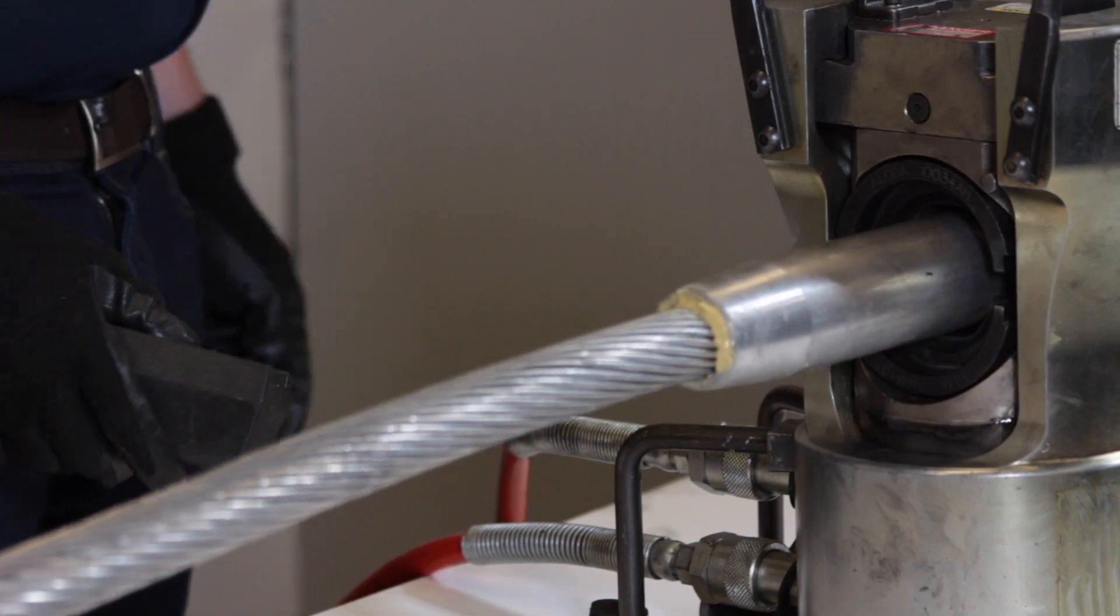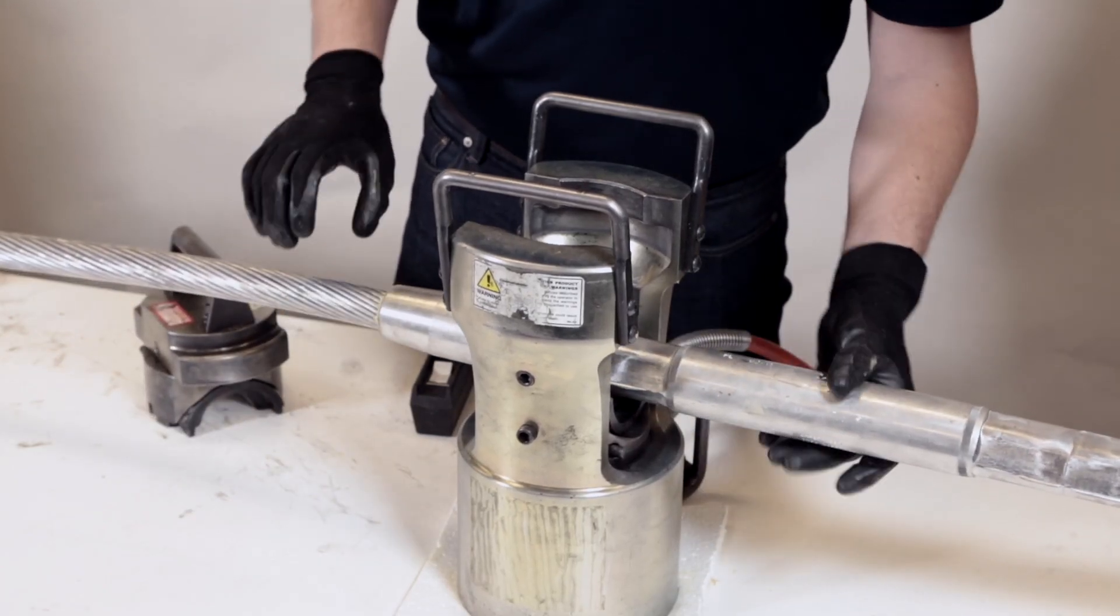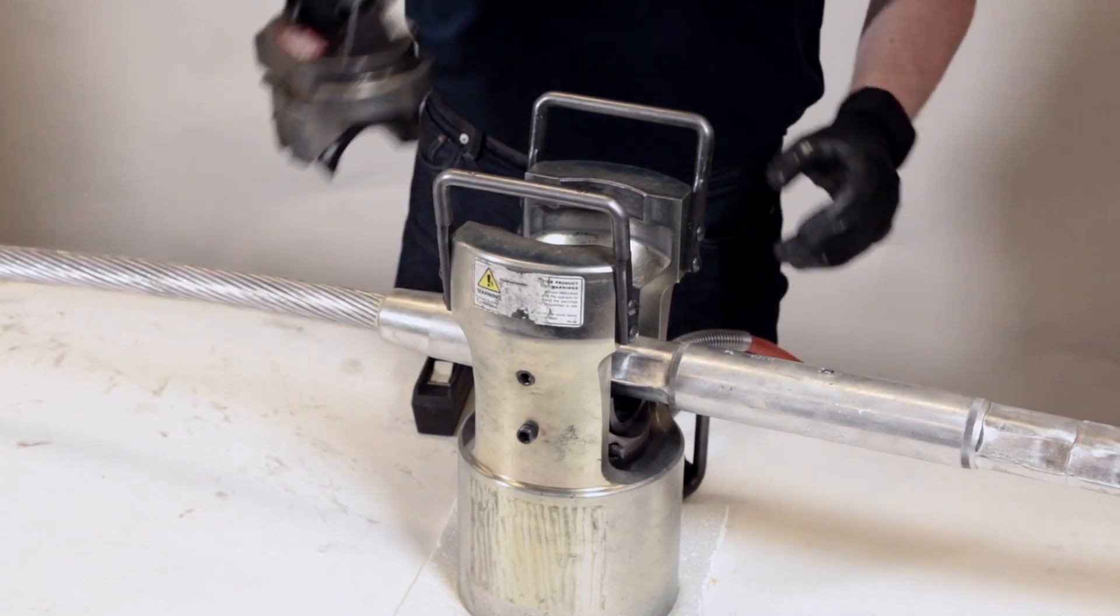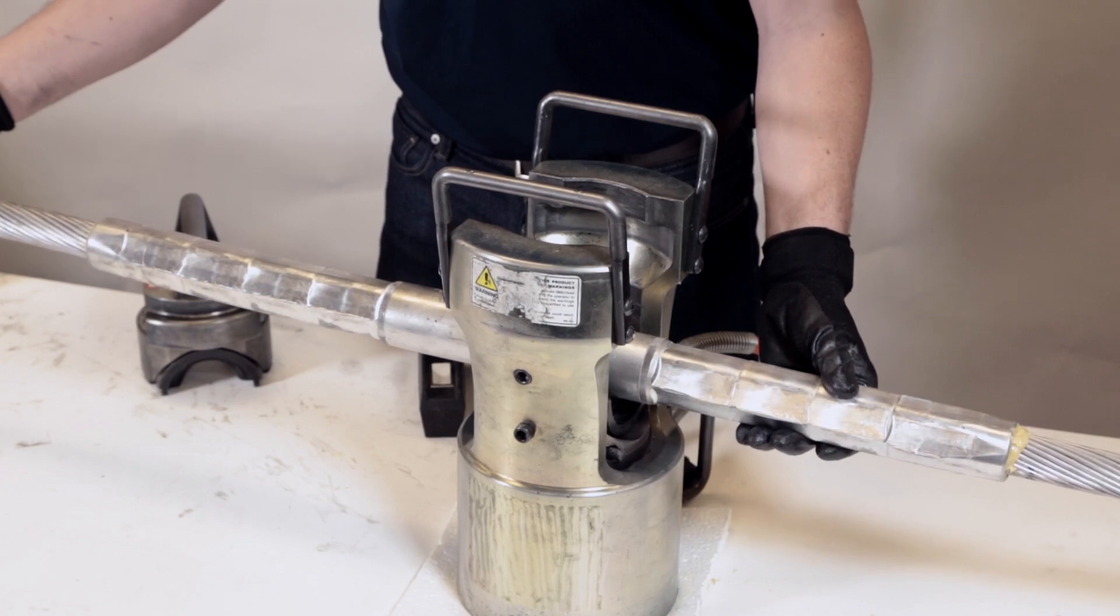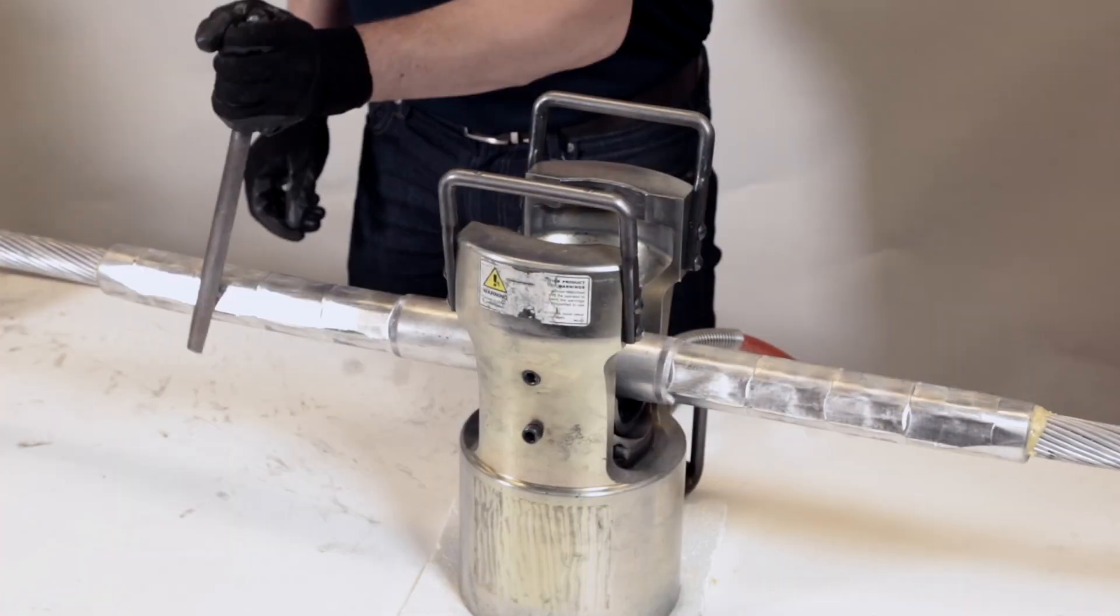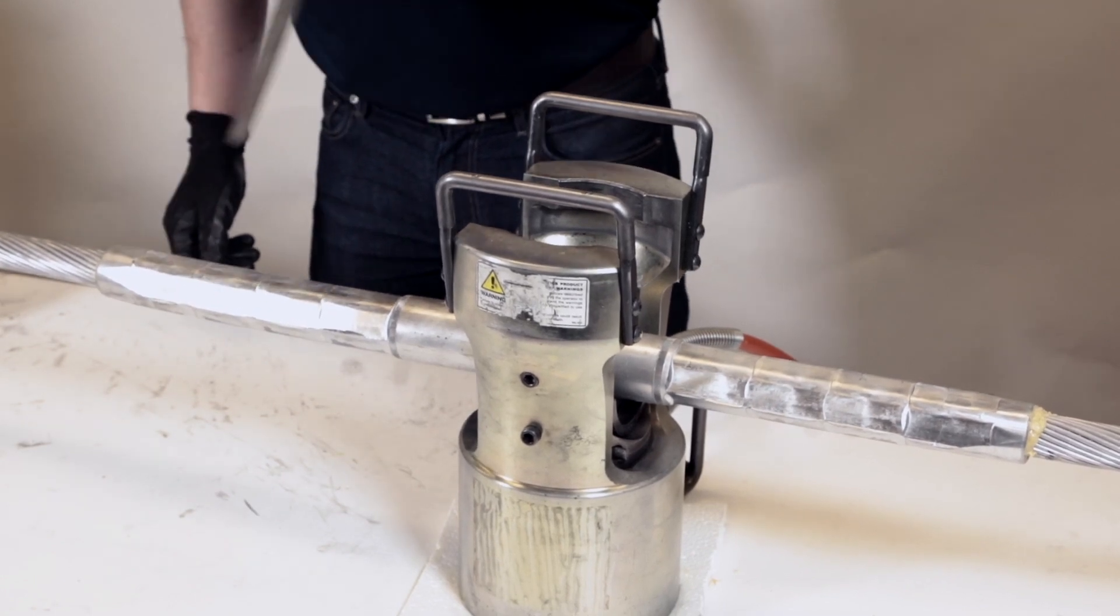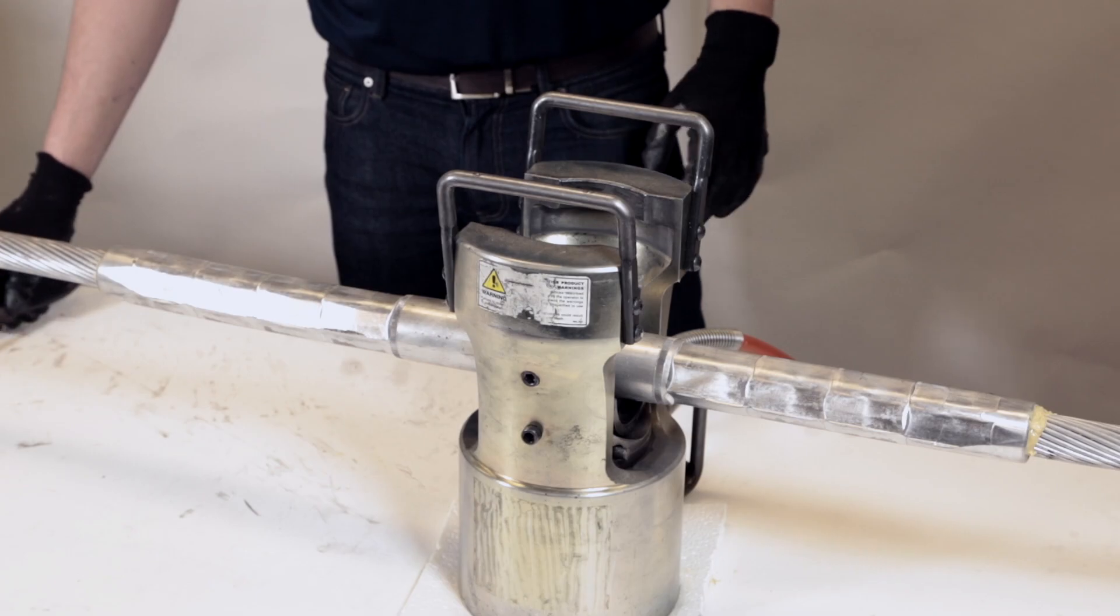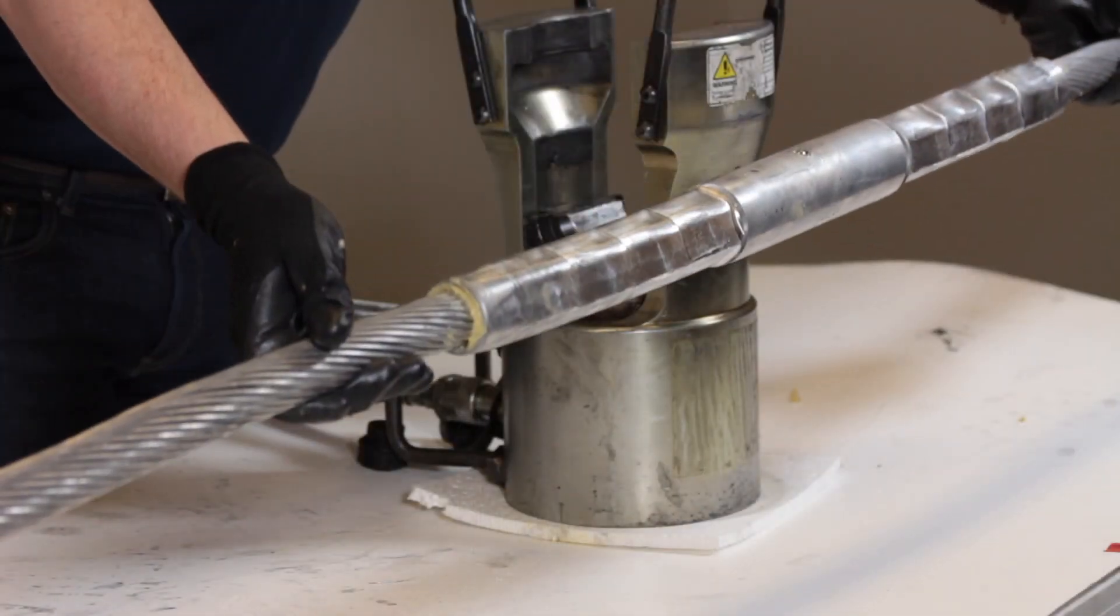Repeat this step for the other side of the splice tube, leaving the center section between the nurls uncompressed. Clean off any excess tape or inhibitor. Any flash left on the aluminum tube after compression should be removed with pliers and sharp edges should be filed to a smooth finish. Once compressed and cleaned, the splice application is complete.